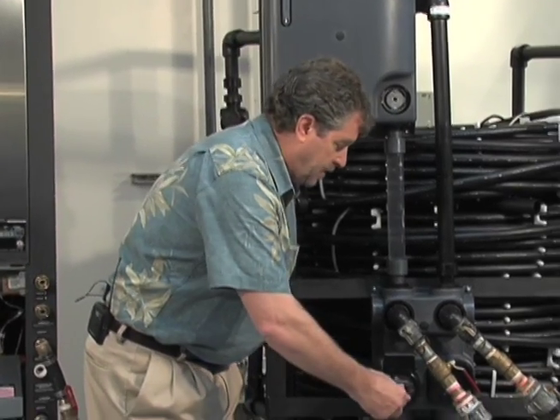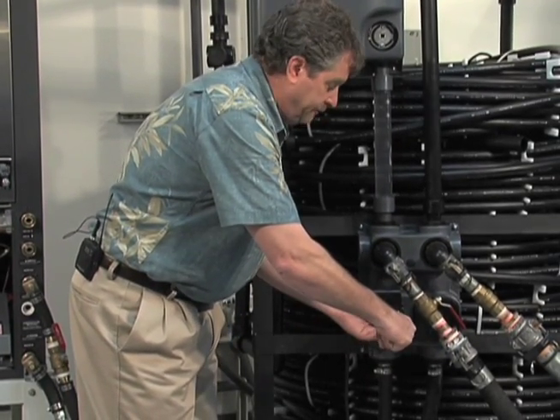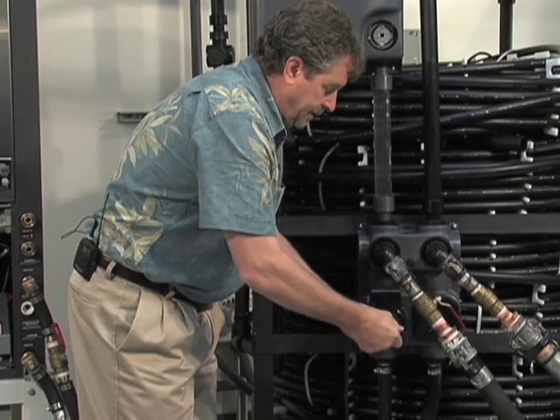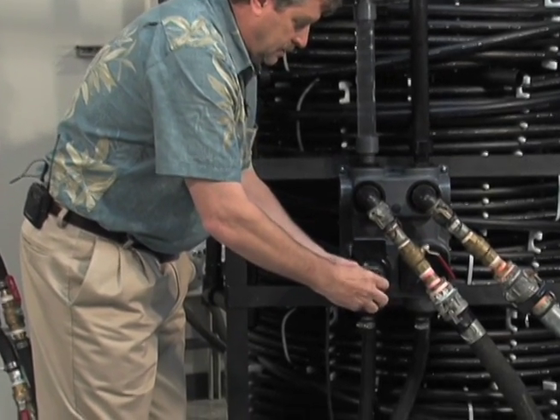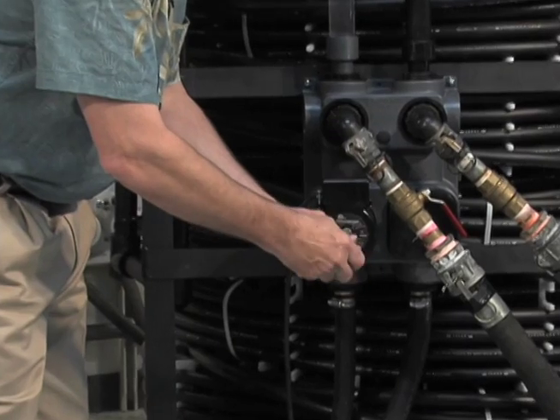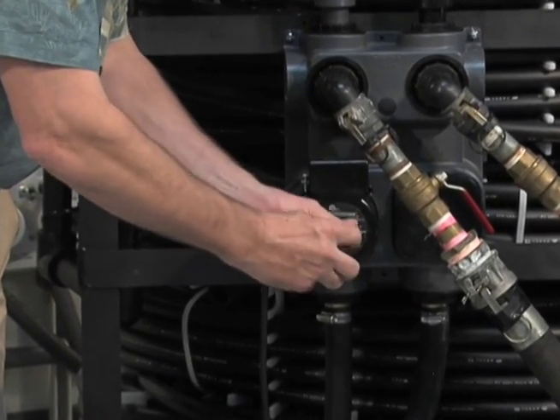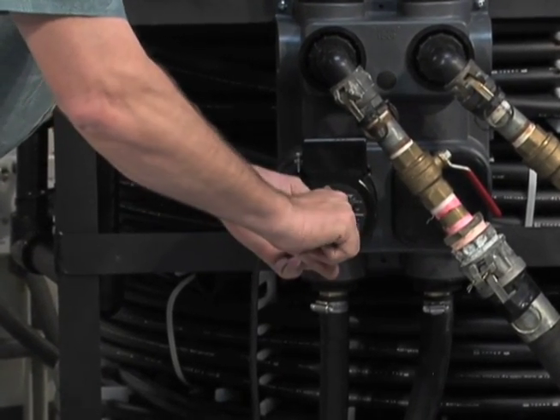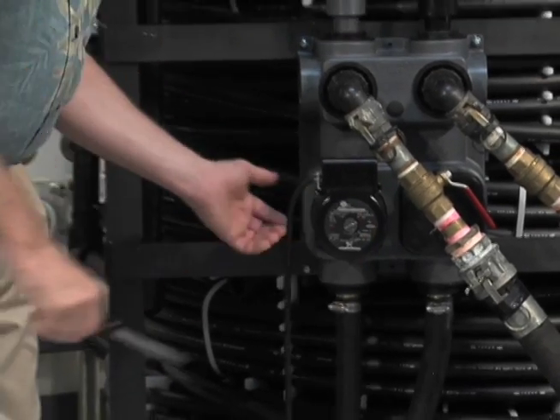Simply take a blade screwdriver, again, while there's fluid pressure on here, loosen it up so you get a little drip, and then just tighten it back up and snug it. Now we've burped the air out of that shaft, we've applied some fluid back to the back part of that bearing. Now you're going to have a pump that's going to give you some good service life.